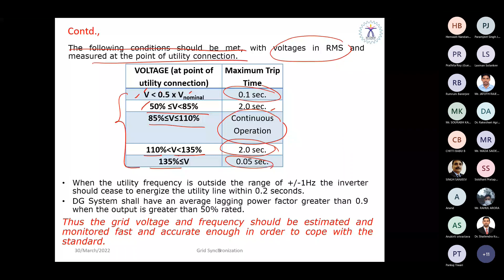So it means we are instantaneously measuring these grid voltages, right? In addition to the voltage, when the utility grid frequency is outside the range of plus or minus 1 hertz, the inverter should cease to energize the utility within 0.2 seconds. Please keep in mind that this point is very important. When the utility frequency is outside the range of plus or minus 1 hertz, the inverter must be disconnected from the utility grid within 0.2 seconds. Of course, it is about 200 milliseconds as far as the IEEE 929-2000 standard is concerned, the recommended practice for utility interface of solar PV systems.